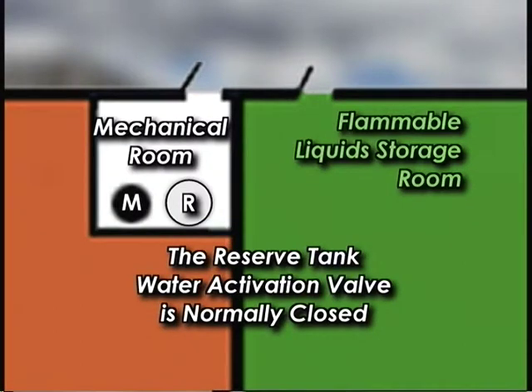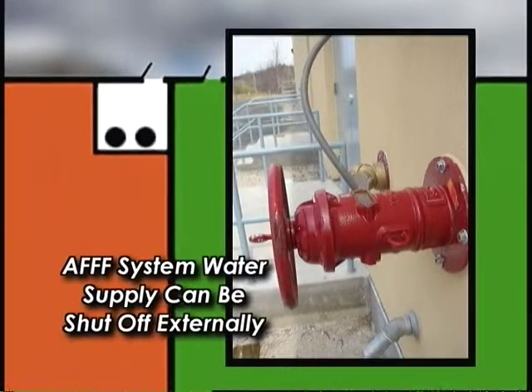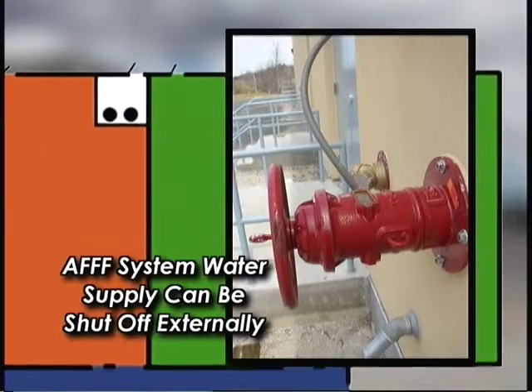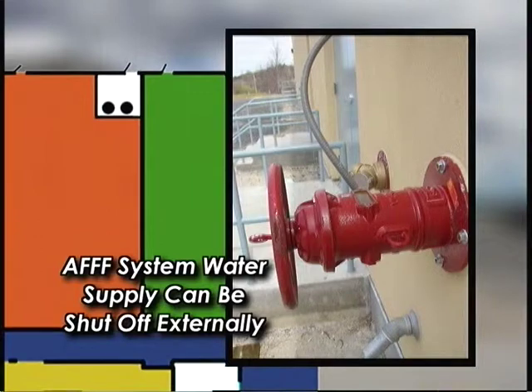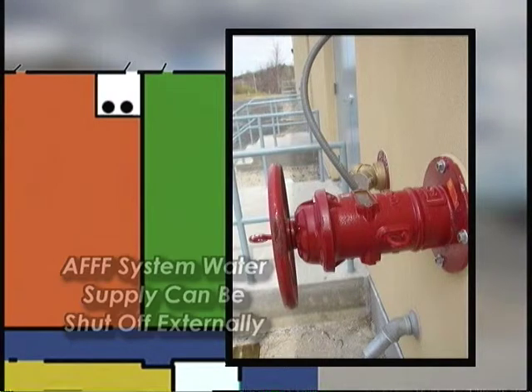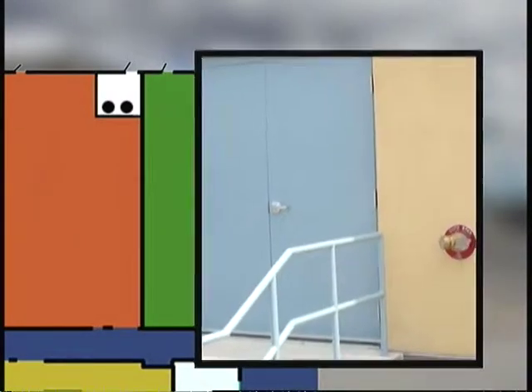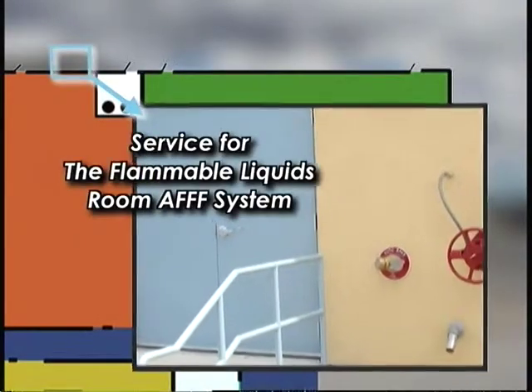The water activation valve on the side of the reserve tank is normally left in the closed position. In order to place this reserve AFFF tank into service, the water activation valve must be opened manually. The AFFF system water supply for the flammable liquid storage space is arranged to allow the water supply to be shut off for the space with the use of outside stem and yoke valves that can be remotely operated from outside the building. These are located adjacent to the mechanical room on the west side of the building.